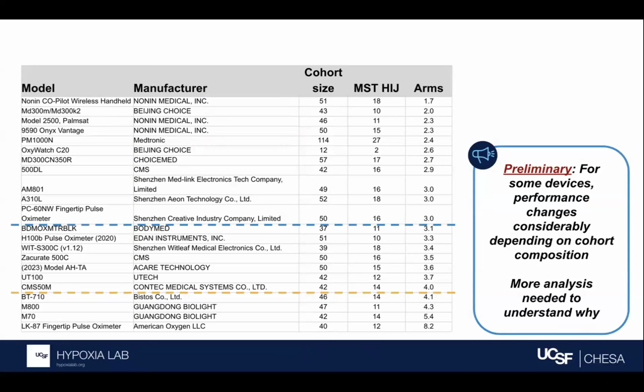Here are some preliminary data on the root mean square error, this statistical metric that is in the regulatory standard. You can see the model in the left column, the manufacturer, the cohort size, and the column that's labeled MST-HIJ. This is study participants with dark skin pigment as defined by Monk HIJ or an ITA threshold of less than -30. So some of these cohorts are not yet at the 33% threshold, which is why these are still preliminary results. And on top of that, we don't yet know what the total cohort size is going to be needed to power each of these.